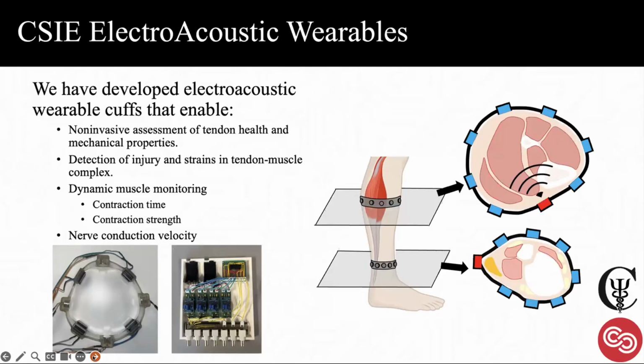So this is just an example of one of our devices, the electroacoustic wearable. And if you look on the right side of the screen, you see that there are multiple transducers, and this is just a mock-up of one of the devices around the patient's calf. And the transducers can send, again, either acoustic or electrical signals. And the transducers can also behave as sensors. So the idea is you send an acoustic wave at a certain frequency through the tissues, and then you measure those acoustic waves after they've passed through the tissues, and they can give you a lot of information about the tissue.